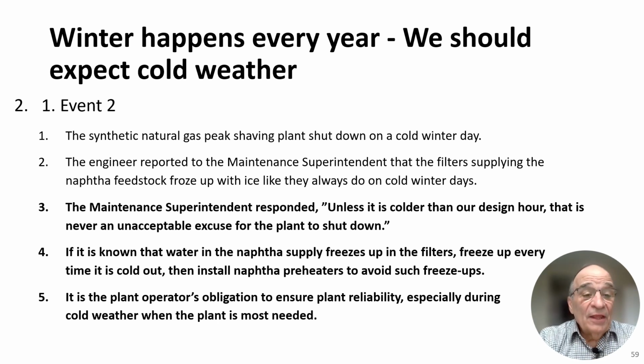Event number two. Synthetic natural gas peak shaving plant shut down on a cold winter day. The engineer reported to the maintenance superintendent that the filters supplying the naphtha feedstock froze up with ice like they do every cold winter day. The maintenance superintendent responded, "Unless it is colder than our design hour, that is an unacceptable excuse for a plant to shut down. If it is known that water in the naphtha supply freezes up the filters every time it is cold outside, then install naphtha preheaters to avoid such freeze ups. It is the plant operator's obligation to ensure plant reliability, especially during cold weather when the plant is most needed." The follow-up to this was that naphtha preheaters were installed.